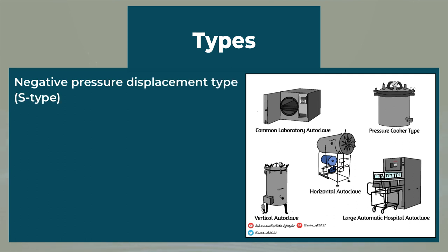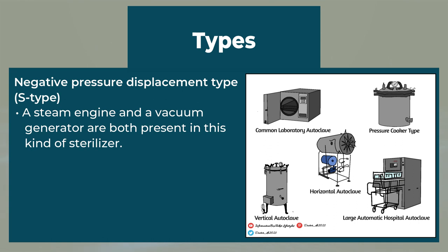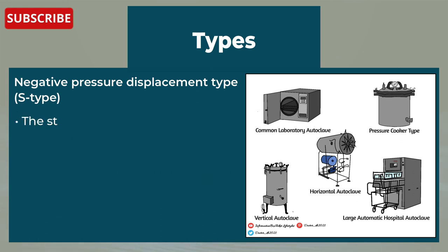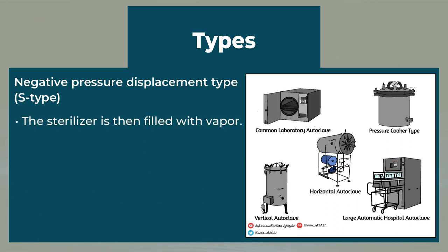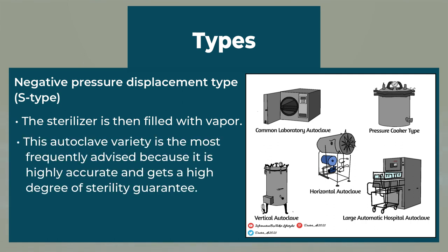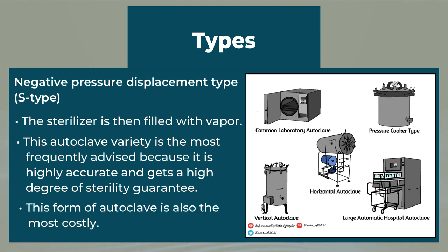Lastly, the negative pressure displacement type. A steam generator and a vacuum generator are both present in this type of sterilizer. The steam generator produces steam while the vacuum generator removes all of the air from the sterilizer, and the sterilizer is then filled with vapor. This autoclave variety is the most frequently advised because it is highly accurate and achieves a high degree of sterility guarantee. This form of autoclave is also the most costly.